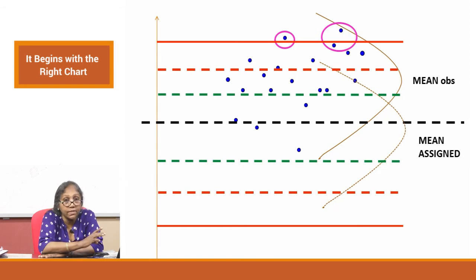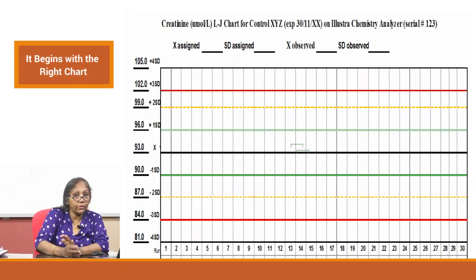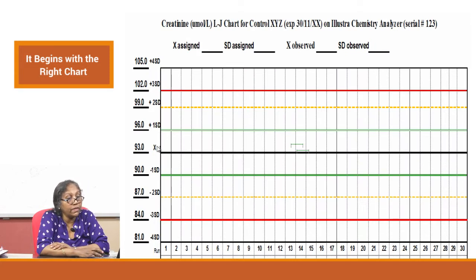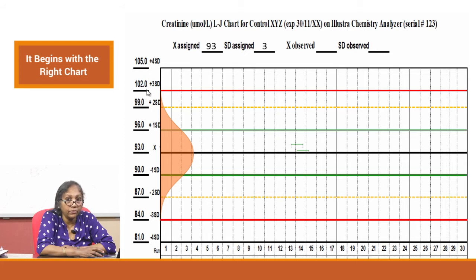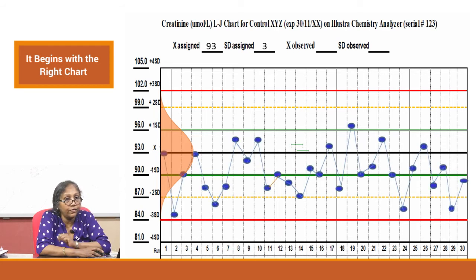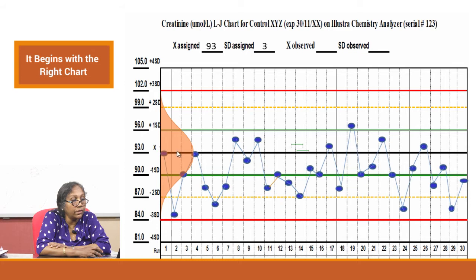Your system is not at fault — what is at fault is that you assigned the wrong values on the chart. For example: an analyte with mean assigned at 93 and standard deviation assigned as 3. You run your QCs with this mean and SD, but over time you find all clustering is happening lower. Your observed mean is actually 90, not 93.